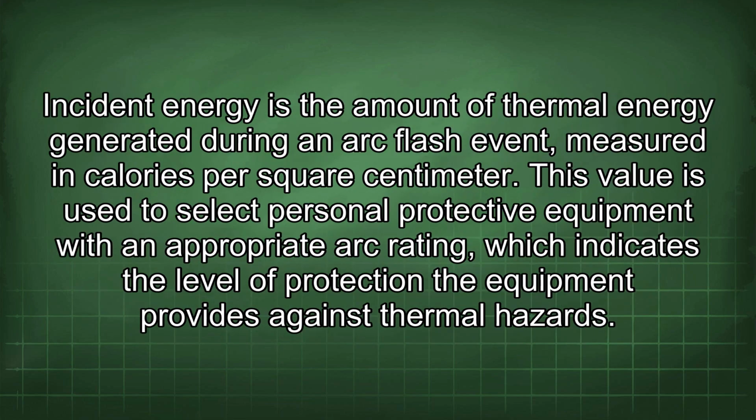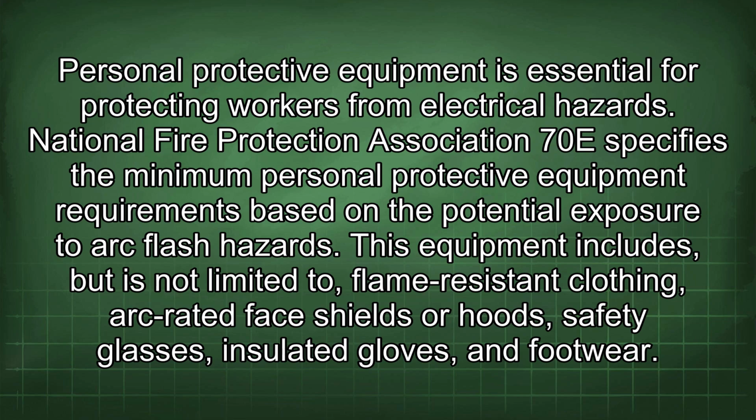Incident energy is the amount of thermal energy generated during an arc flash event, measured in calories per square centimeter. This value is used to select personal protective equipment with an appropriate arc rating, which indicates the level of protection the equipment provides against thermal hazards. Personal protective equipment is essential for protecting workers from electrical hazards.